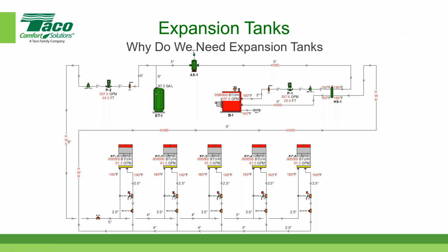At what point is this critical? Plus or minus 10 PSI, or is there a value? My answer to that is that the pre-charge pressure needs to be calculated carefully and it needs to be precise. If the minimum pressure at the expansion tank location by calculation, the calculation is done properly, if it needs to be 50 pounds, then that's the pre-charge pressure. I wouldn't make it higher or lower, I would make it at 50 pounds.